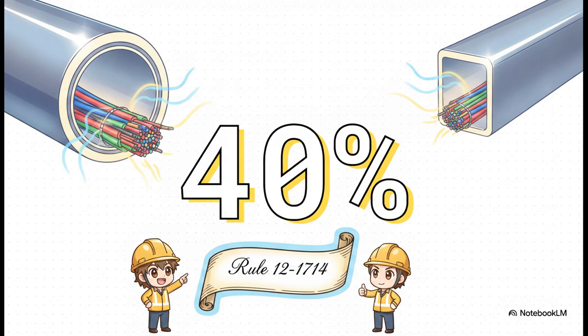Rule 12-1714 is basically the golden rule for conductor fill here. It states that the aggregate cross-sectional area of your insulated and bare conductors, and yes, that includes their insulation, cannot exceed 40% of the interior cross-sectional area of the raceway. This 40% rule is a pretty standard baseline across a lot of conduit types in the CEC. It's there to ensure proper heat dissipation and to make sure you actually have enough room for a smooth wire pull without tearing up your jackets.